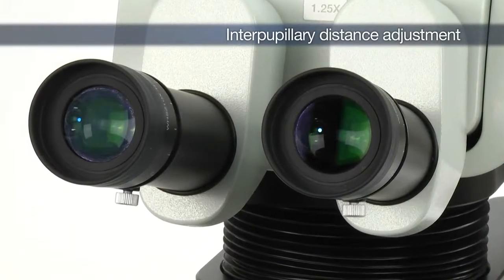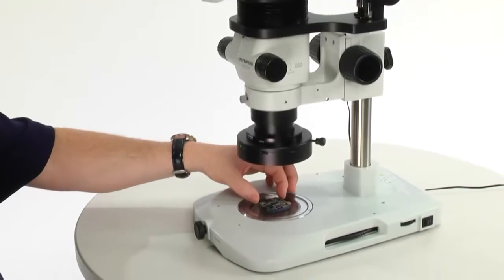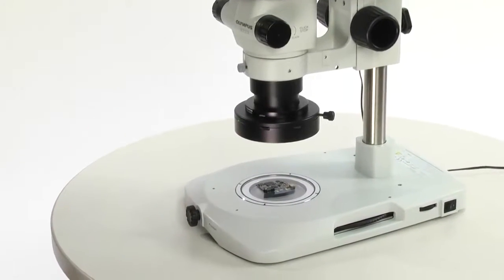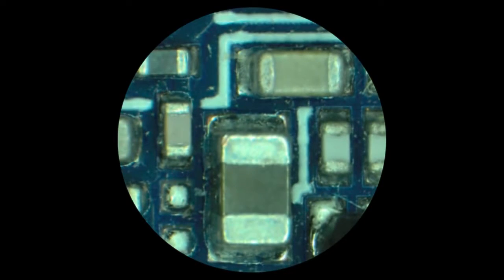Adjusting the interpupillary distance is necessary to obtain proper binocular vision. First, place a flat sample on the stage, adjust the lighting, and bring the sample into focus.